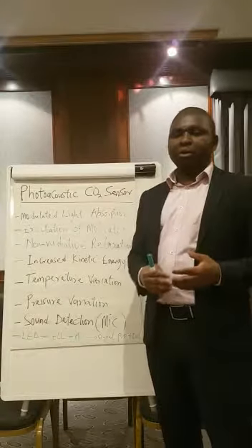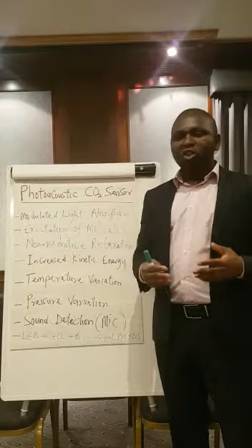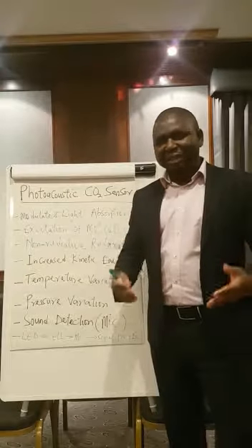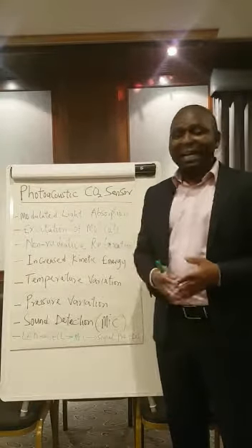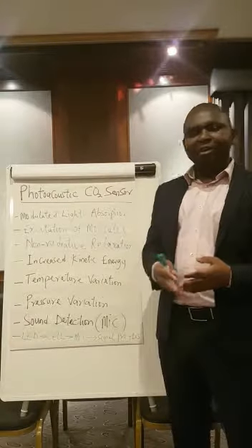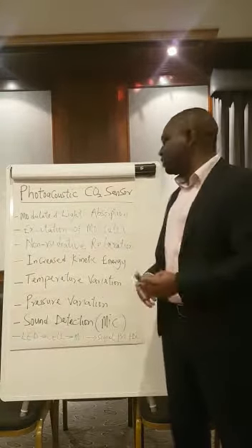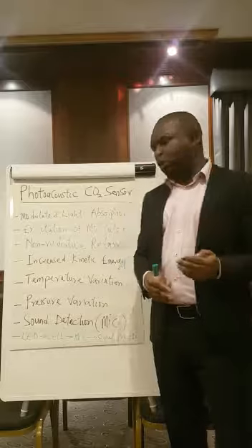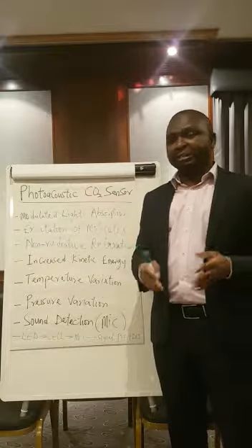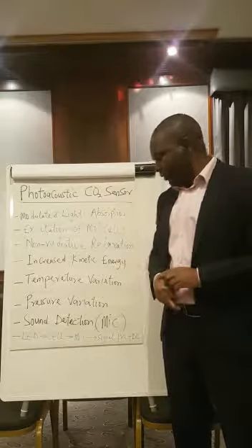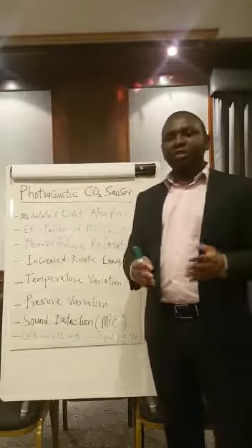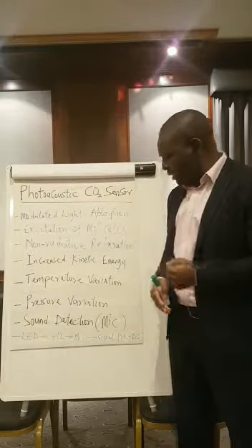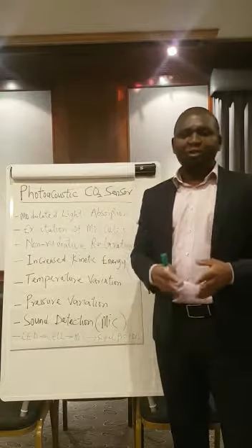Now, this is also called collisional relaxation. This is where the molecules collide with one another, and that causes an increase in kinetic energy of these molecules. This increased kinetic energy actually leads to an increase in temperature, and there's going to be variation of that temperature, which is based on the frequency of modulation of the radiation. Now, the increased temperature also leads to increased pressure within the cell or the chamber where the CO2 is. Now, this pressure variation leads to a generation of an acoustic signal, and this acoustic signal can be detected through the use of a microphone.